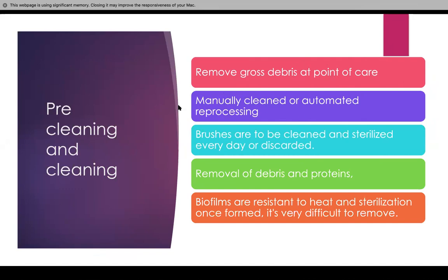Manually cleaned or automated reprocessing uses the ultrasonic cleaner. Brushes are to be cleaned and sterilized every day or discarded. Removal of debris and proteins is essential, as biofilms are resistant to heat and sterilization once formed — it's very, very difficult to remove them. That is why all of this is very important to follow.